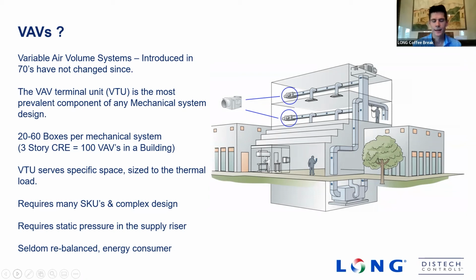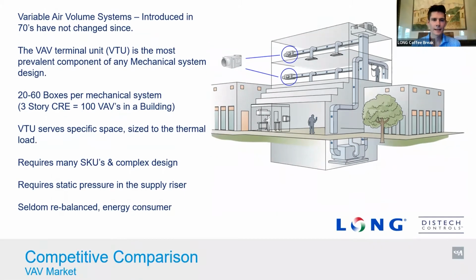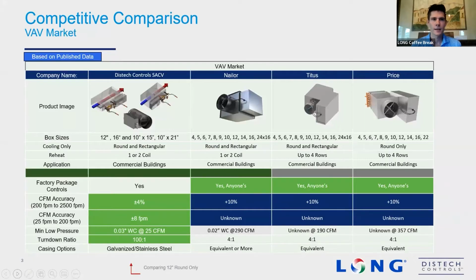Thank you, Jim. Yeah, that last point there. Often when we all go into buildings, it's very rare that you see a building get rebalanced after TIs are built out. And as we know, typically within a year, a building is out of balance on both the air and the water side. So a lot of good points there. The next slide, Lance, I'm going to ask you if you could help us go through some of the differentiators between a traditional VAV box and what we're talking about here today with the smart air control valve.